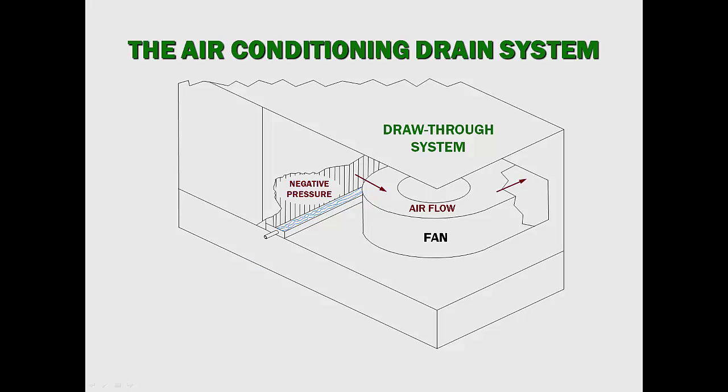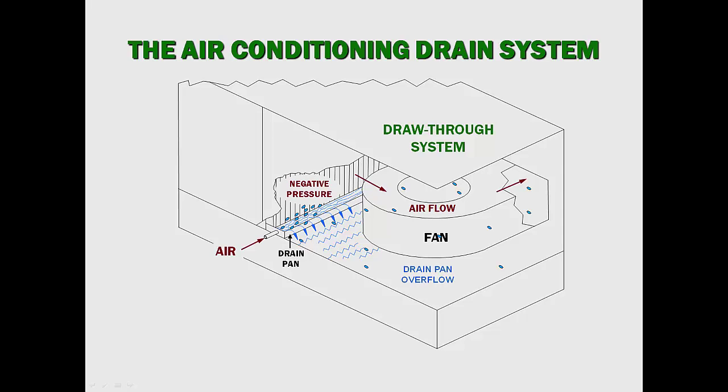To be effective, a drain system must overcome the pressures and airflow conditions created inside the drain pan compartment by the fan. Without an effective drain system, condensate flow is adversely affected. In draw-through systems, as illustrated here, water is blown back into the air handler, and drain pan overflow is common.